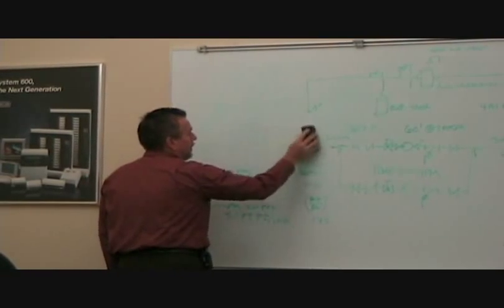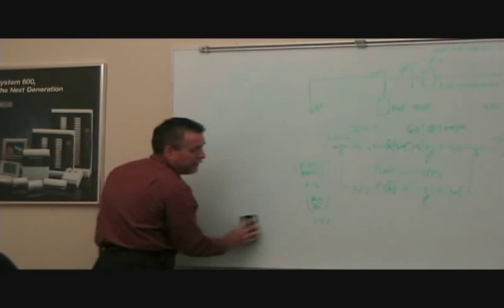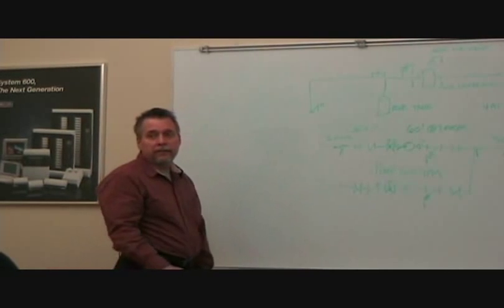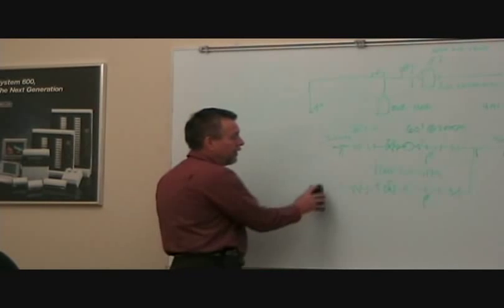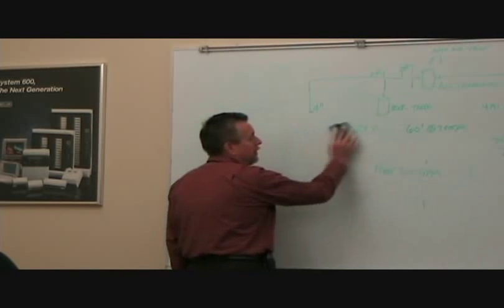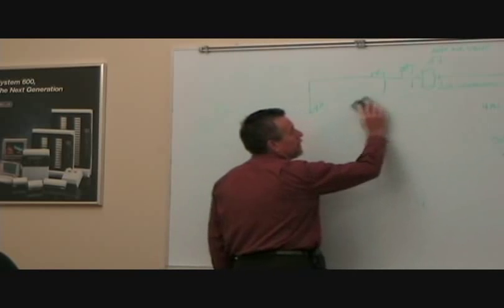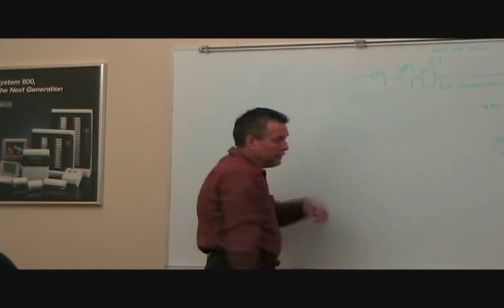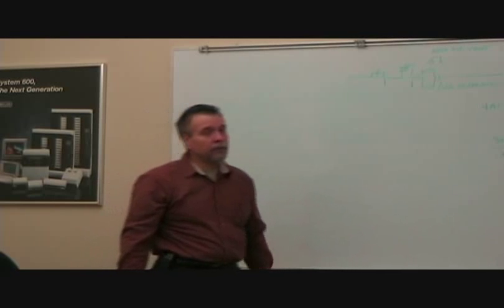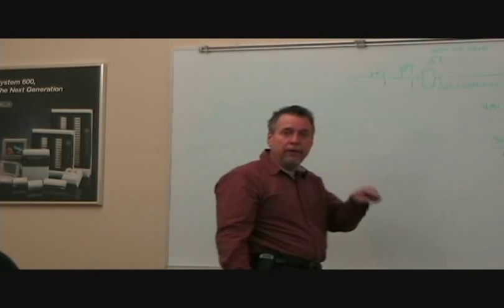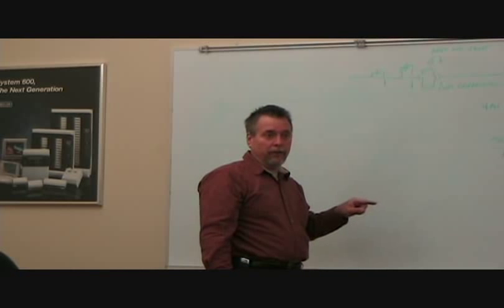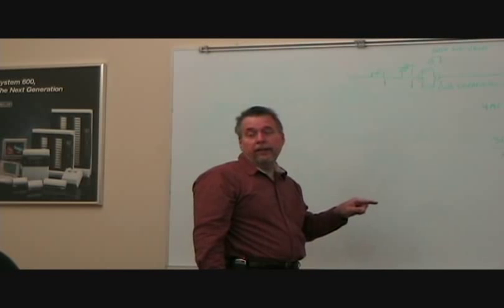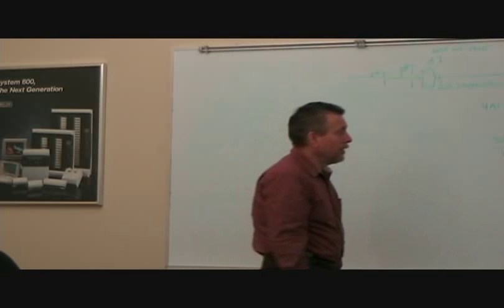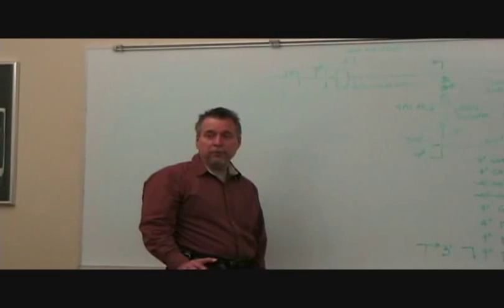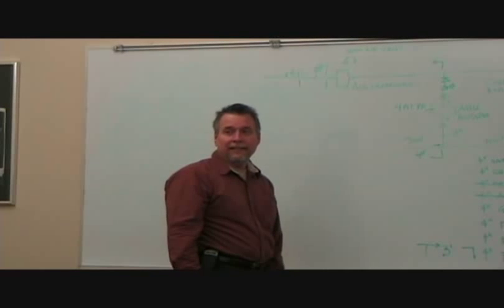How often do you see a condenser water pump running in a vacuum? 20% of the time. I know some buildings do. Yeah. You've got not big enough pipe, cooling tower's not above the pump enough. Operating in a vacuum is not necessarily a bad deal if you compare it to, and I'll show you on the net positive suction curve of your pump. So operating at a few feet of vacuum, it may not necessarily be that bad a deal. Operating at 10, 20 feet of vacuum, a pump's gonna make a lot of noise.